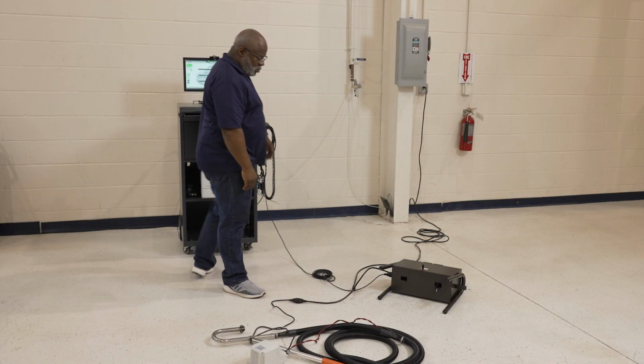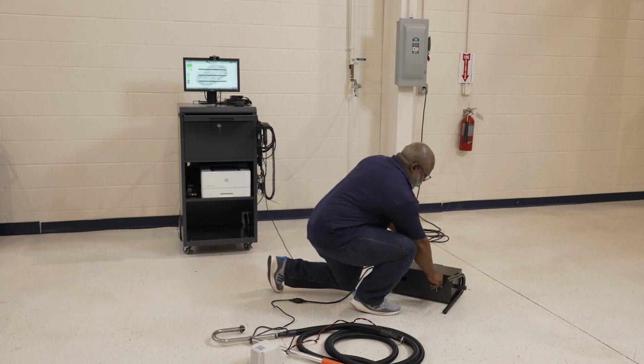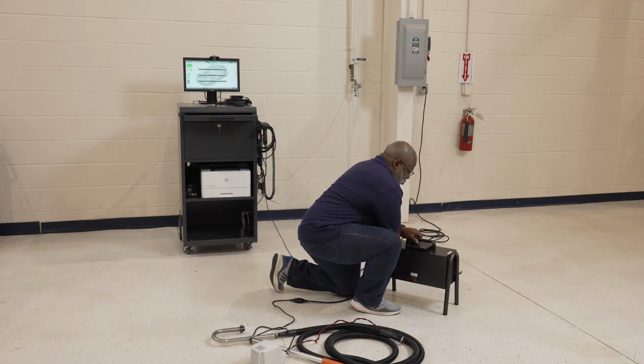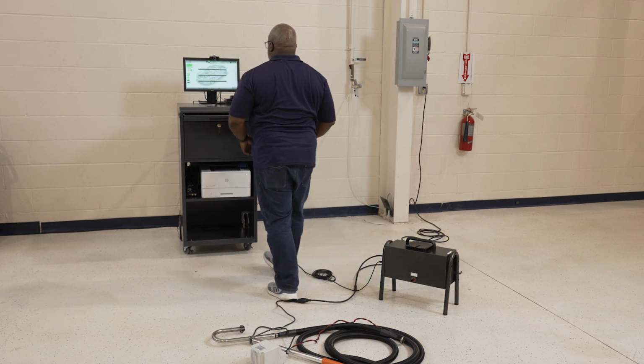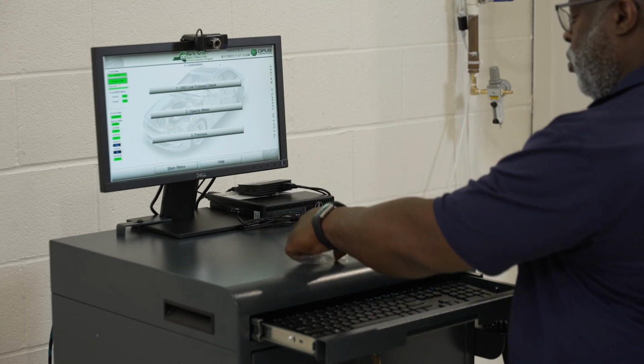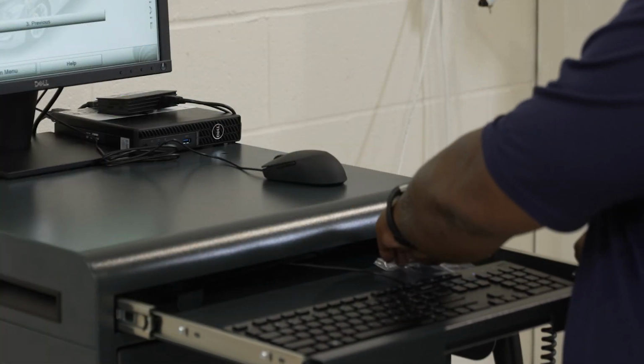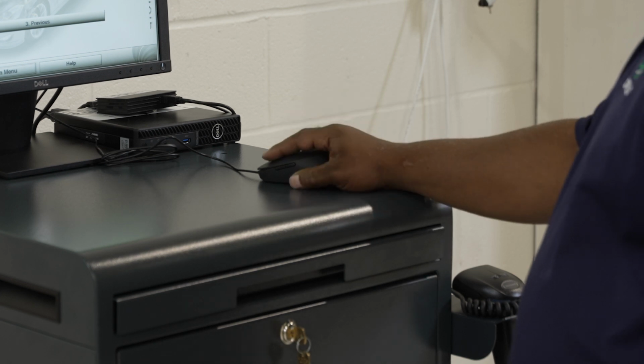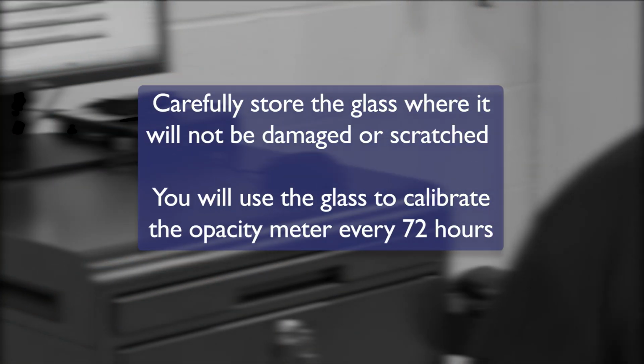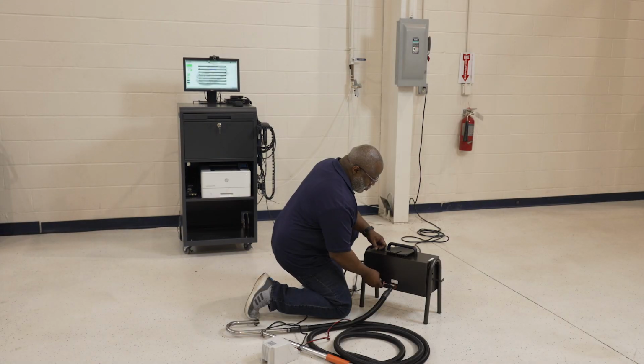Remove the reference glass from the bottom of the opacity meter. Return the meter to the upright position. Place the reference glass back into its protective sleeve and carefully store the glass where it will not be damaged or scratched. You will use the glass to calibrate the opacity meter every 72 hours. Reconnect the heated exhaust sample hose.